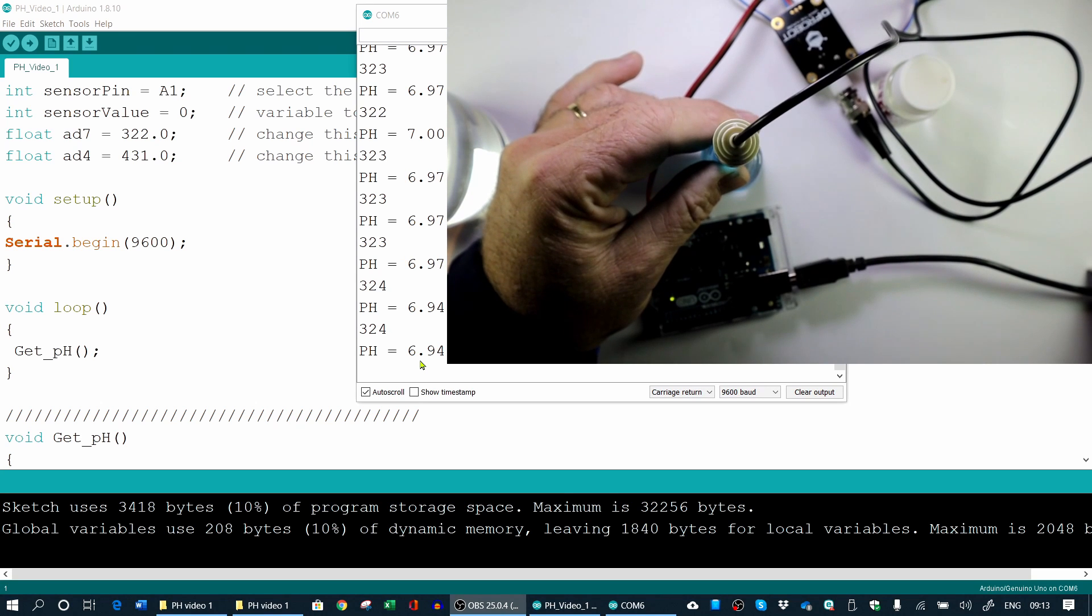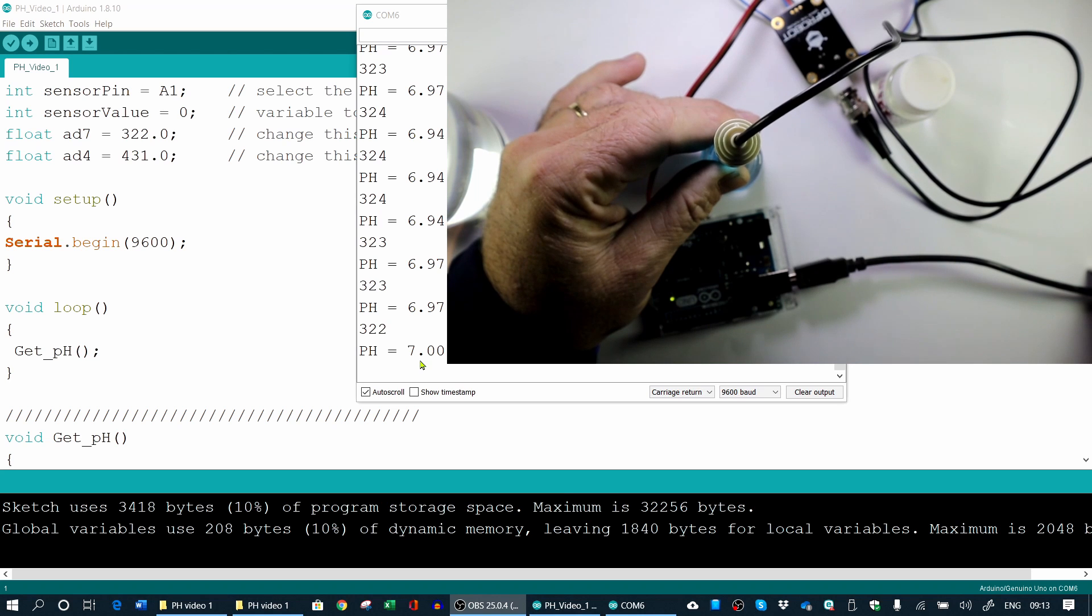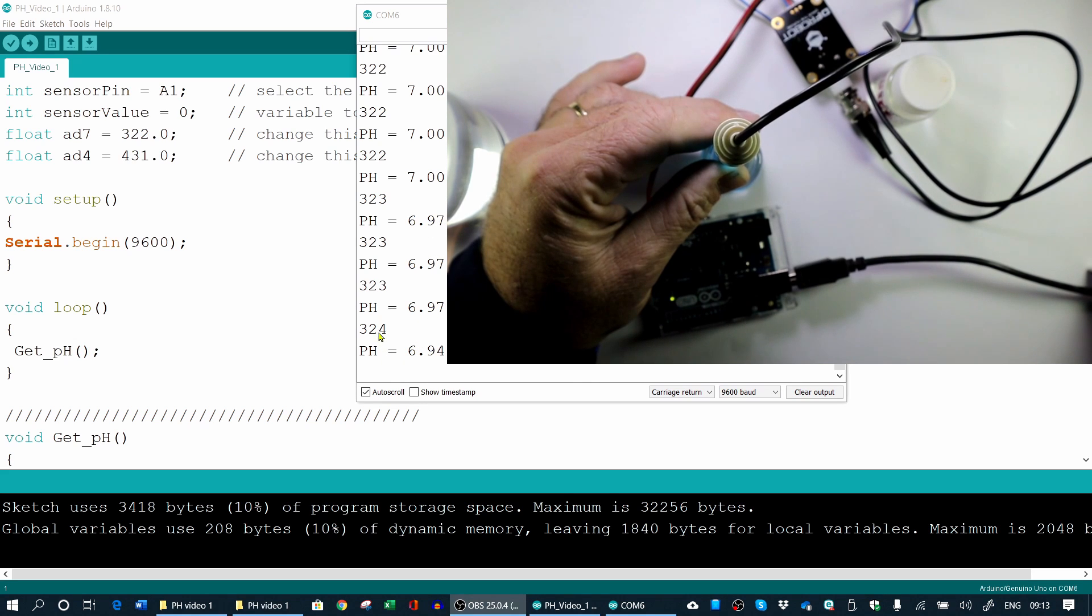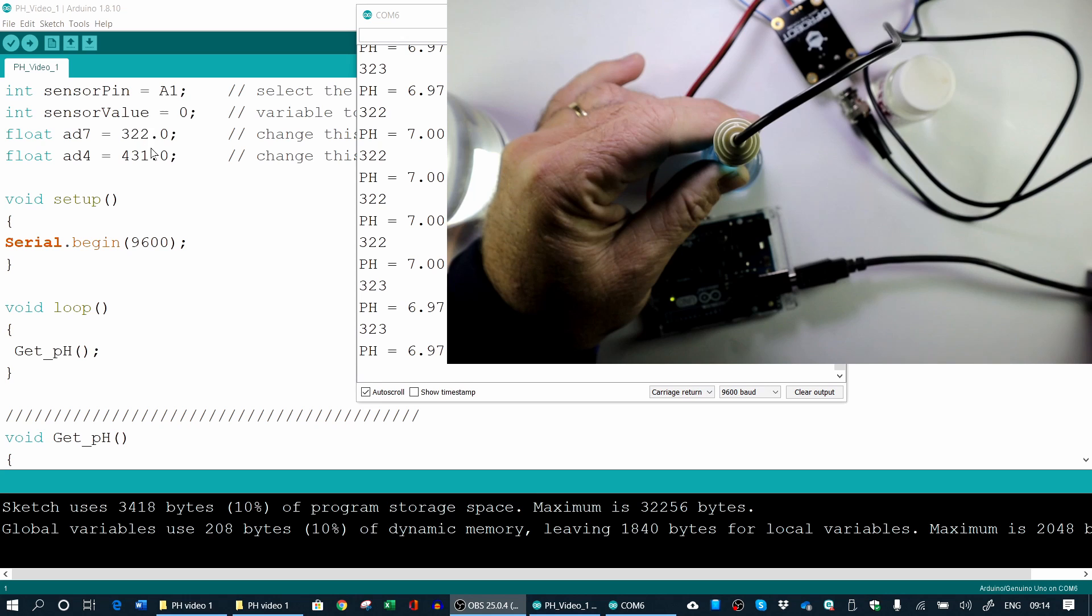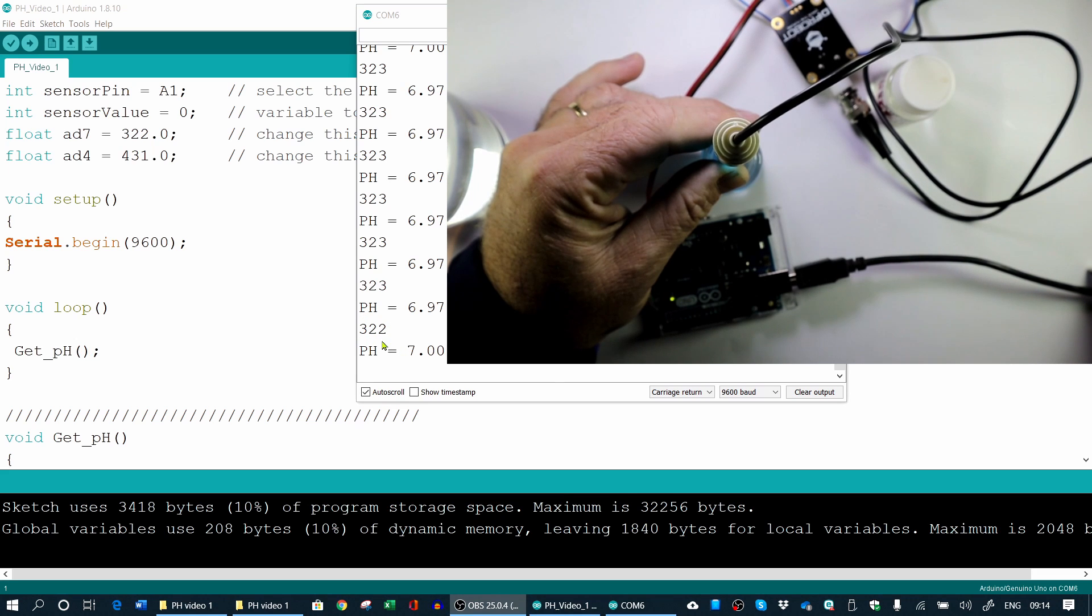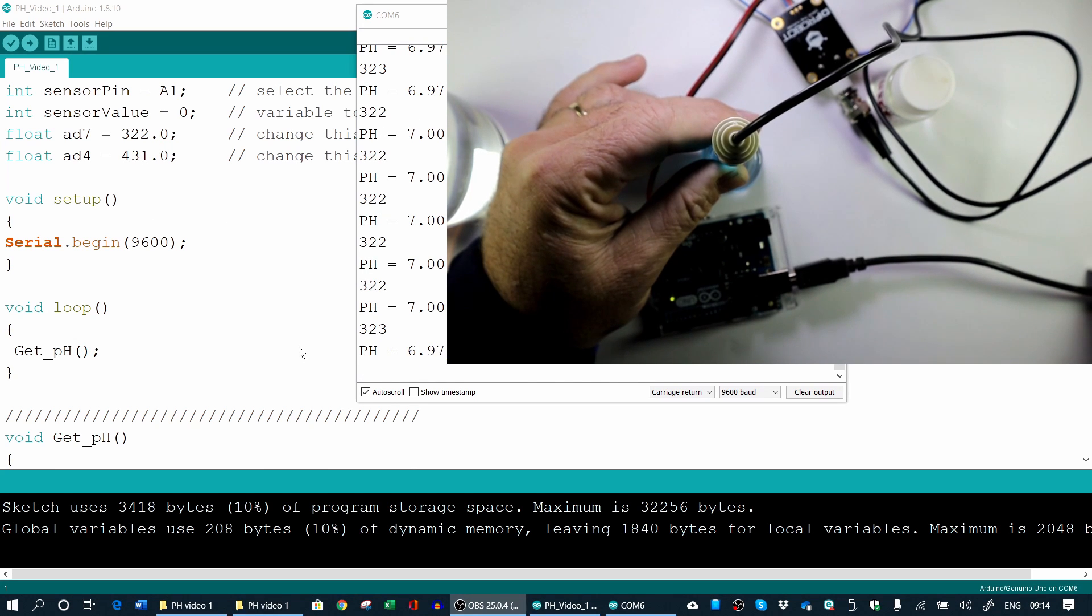The manufacturer suggests that you leave it in the buffer solution for at least a minute for it to stabilize. And there you can see it's almost seven. So it's actually very well calibrated. If there were a difference between this value and that one there for the seven, then we would have changed this value to the value that you read here. But you can see 322 and the seven pH. That's absolutely correct.